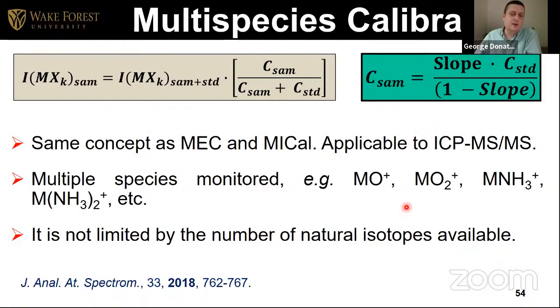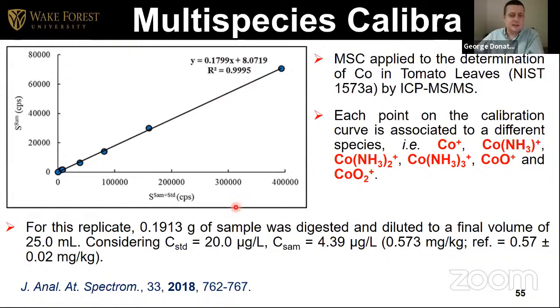So in this example, you have a quadrupole, then you have a reaction cell and another quadrupole. So in the reaction cell, you produce many species of your analyte. It could be an oxide, double oxide, or an ammonia cluster. Here's an example for cobalt applied to tomato leaves, reference material of tomato leaves. Each of those points corresponds to one of those species: cobalt by itself, with ammonia, with two ammonias, and so forth.